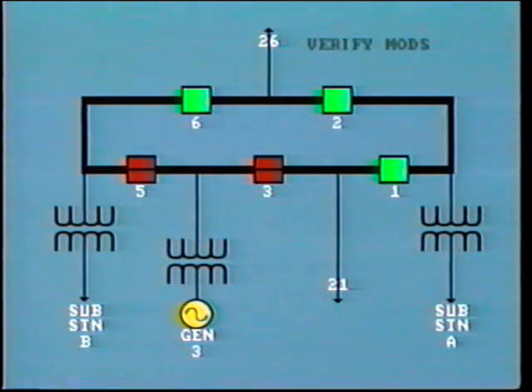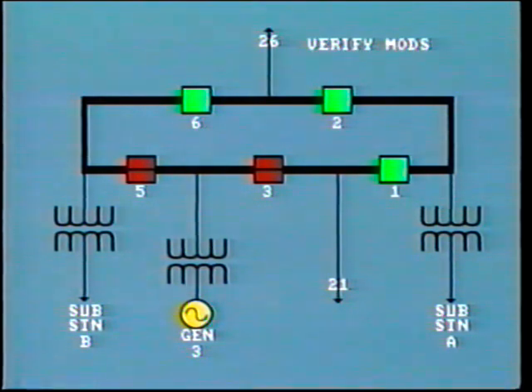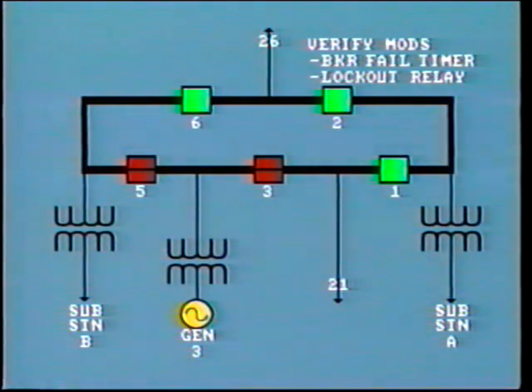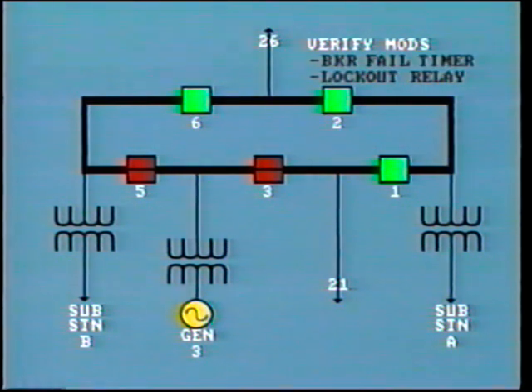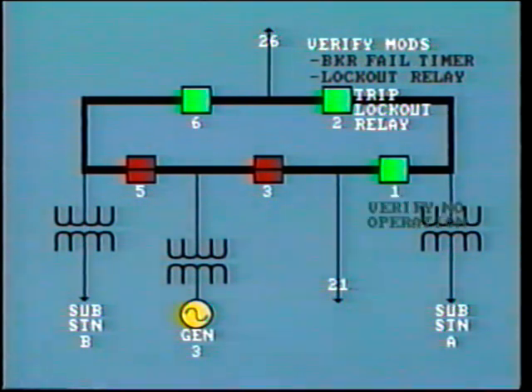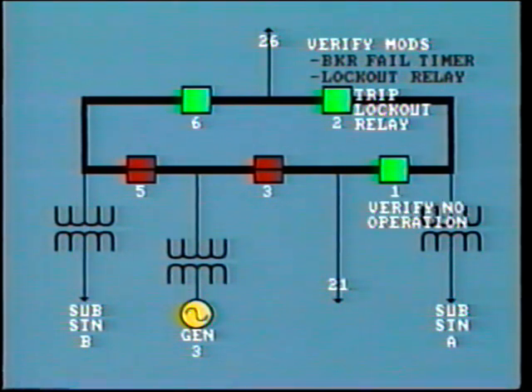The technicians' task was to verify modifications which had already been made to the existing breaker failure relaying for breaker 2. Specifically, they had to check that the breaker failure timer and an associated lockout relay were out of service, and that the output circuits were disconnected. The task looks simple enough. Breakers 2 and 1 were already open, so all they needed to do was to trip the lockout relay and verify no operation of breaker 1 trip circuit.